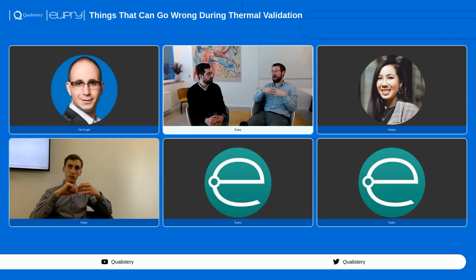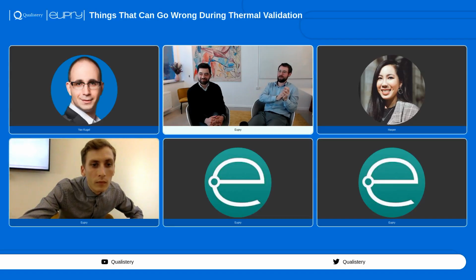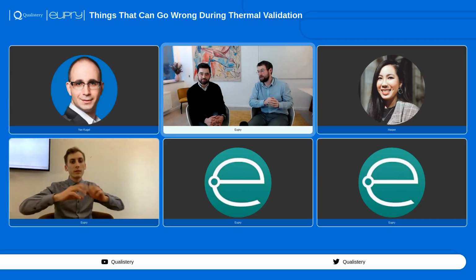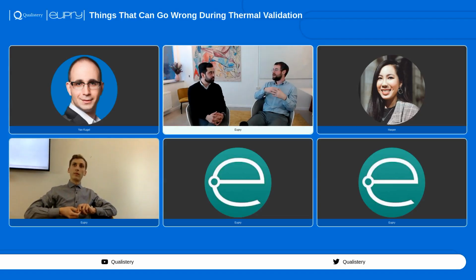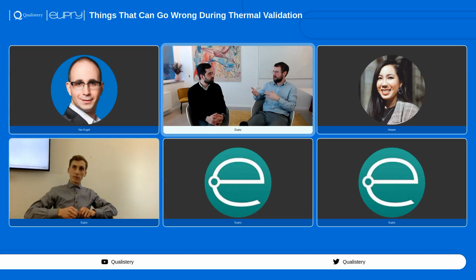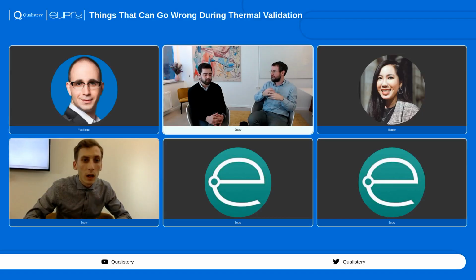Also, how harsh do you treat your sensors? For typical warehouse storage, the acceptable range is 15 to 25 degrees. That's the ideal temperature to store a sensor in, where it will have minimum drift. But then again, you have cases like we've seen a lot lately, ULT freezers stored at -80 degrees. That's more harsh on a sensor, and you'll experience more drift. But it all boils down to the risks associated with it.